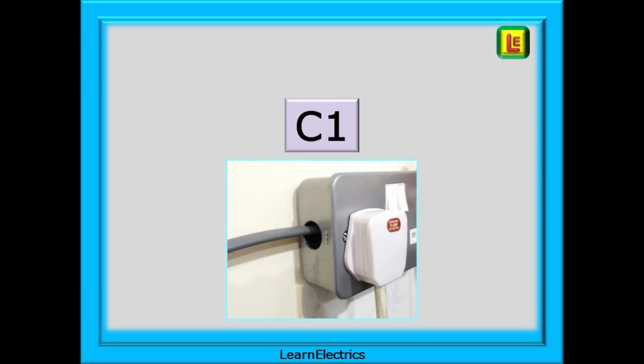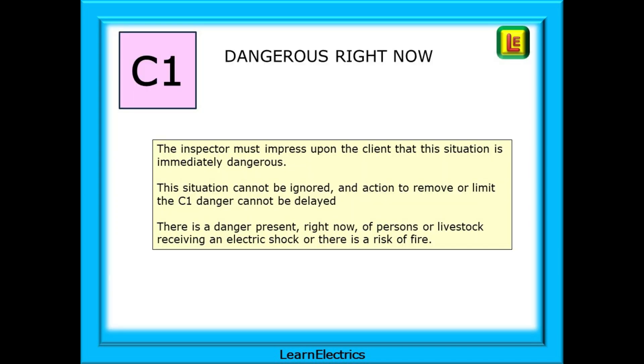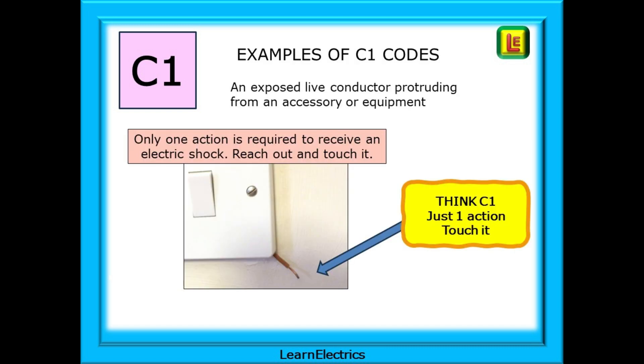Taking a closer look at the C1 observation code: C1 is dangerous right now. The inspector must impress upon the client that this situation is immediately dangerous, that it cannot be ignored, and that action to remove or limit the C1 danger cannot be delayed. There is a danger present right now of persons or livestock receiving an electric shock, or there is a risk of fire. Some examples of C1 codes: an exposed live conductor protruding from an accessory or some equipment. This is immediately dangerous because only one thing needs to happen to receive an electric shock — just reach out and touch the wire. I think of C1 as just one action: touch it. And I find that this helps me to visualise the code better — C1 for one action.